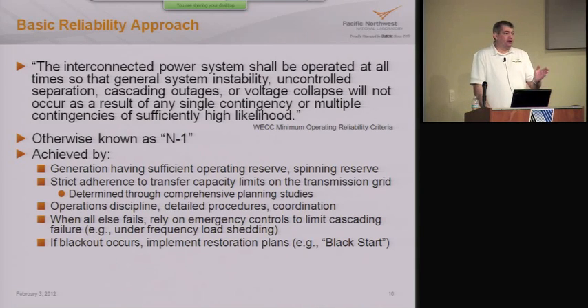They have different categories of contingencies - categories A, B, C, and D - that are spelled out. NERC and the regions have criteria for what these are and how they're defined. Essentially, for a most likely type of outage, like a loss of a power line, you need to recover that without shedding firm load. That's the criteria. But more complicated or less likely events, like a category D, might be a loss of a complete substation with all the lines in and out of it. You can shed firm load in response to that, but you can't introduce a cascading failure, so you need to have protection schemes in place to prevent that.